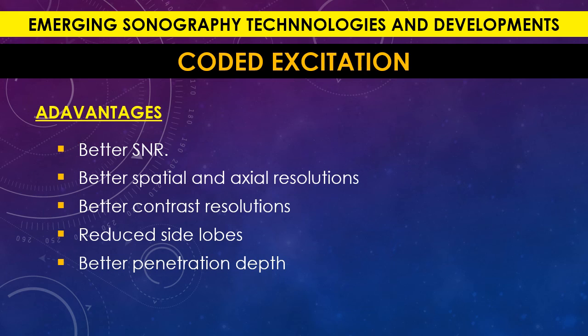So in general, what are the advantages of coded excitation? What are the benefits of coded excitation? It has a better SNR, better spatial and axial resolution, better contrast resolution, reduced side lobes, and better penetration depth.